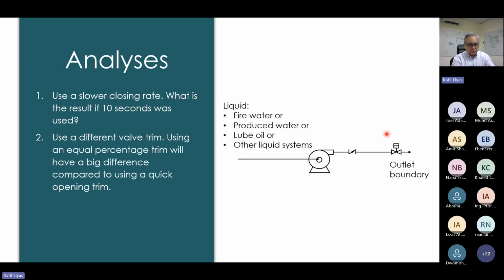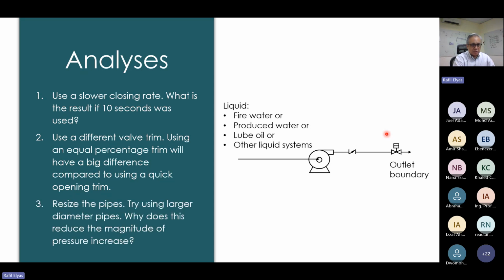If we have a different valve trim, say for example a linear valve versus an equal percentage valve, it's the opposite of a quick opening. It's a quick closing valve. So in some of the cases, we might have to take a look at the stroke time of the valve. In some cases, we have an issue and might have to resize some pipes. We had a recent case where unfortunately we had to go back to the customer and say that we've got some issue on the sizing. We've got some liquid surge issues. We need to revisit the pipe diameters for certain sections.